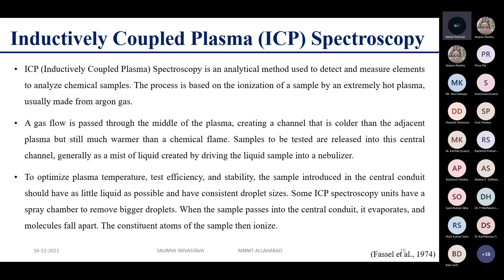A gas flow is passed through the middle of the plasma, which creates a channel, and it is colder than the adjacent plasma, but warmer than the chemical flame. And the samples that have to be tested are released into this central channel. To optimize the plasma temperature, test efficiency, and its stability, the sample which is introduced in the central conduit should have as little liquid as possible, and it should have a consistent droplet size.